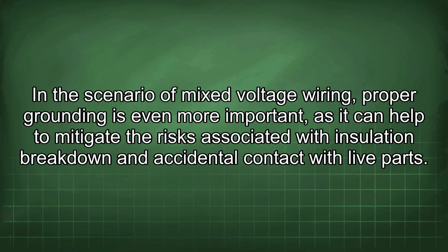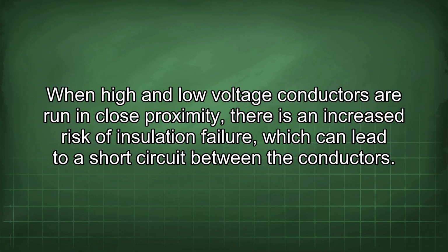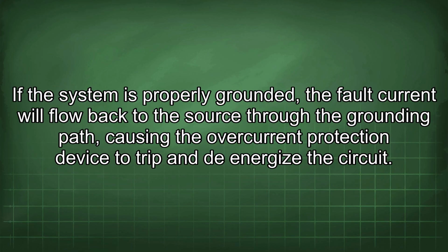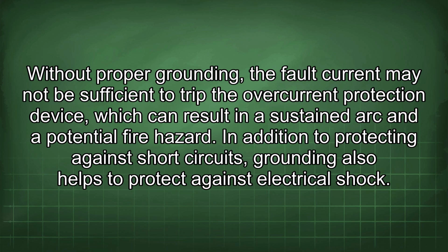In the scenario of mixed voltage wiring, proper grounding is even more important, as it can help to mitigate the risks associated with insulation breakdown and accidental contact with live parts. When high and low voltage conductors are run in close proximity, there is an increased risk of insulation failure, which can lead to a short circuit between the conductors. If the system is properly grounded, the fault current will flow back to the source through the grounding path, causing the overcurrent protection device to trip and de-energize the circuit. Without proper grounding, the fault current may not be sufficient to trip the overcurrent protection device, which can result in a sustained arc and a potential fire hazard.